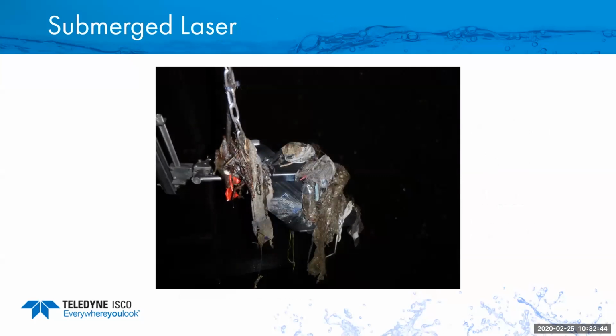Let me show you what we do when it goes underwater. I'll apologize to those of you getting ready for lunch. This is Detroit, Michigan, and it's a big 14-foot channel, and you notice the log cable on that. So the laser can handle submergence. It will handle 6 feet for 72 hours. We have had them in much worse applications than that. Most of the time, the only thing you have to do is maybe clean the stuff that's hanging off the nose.